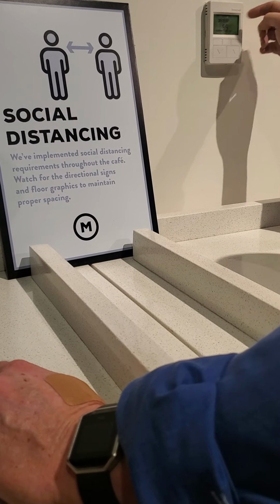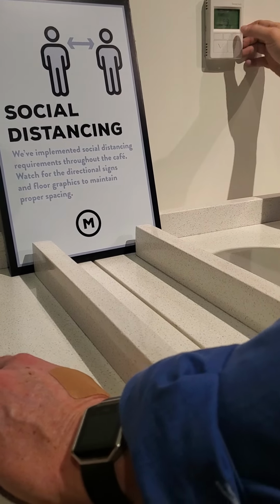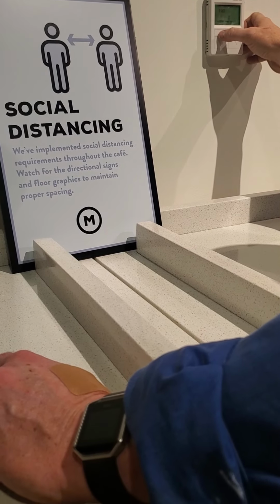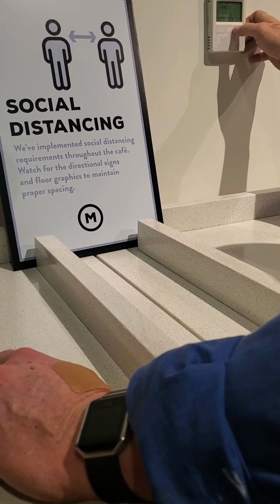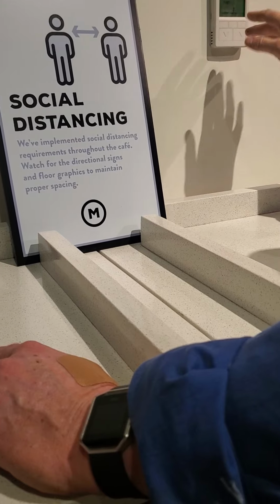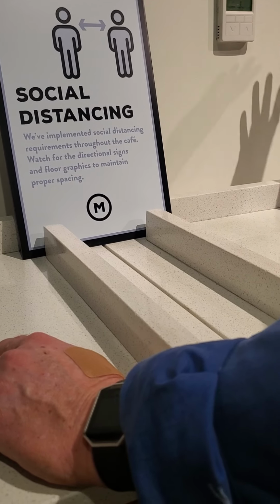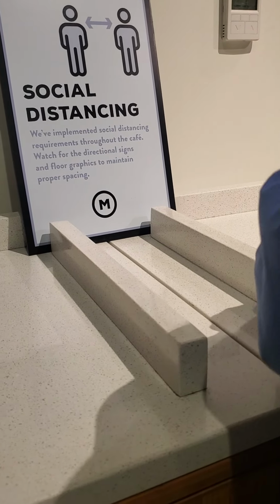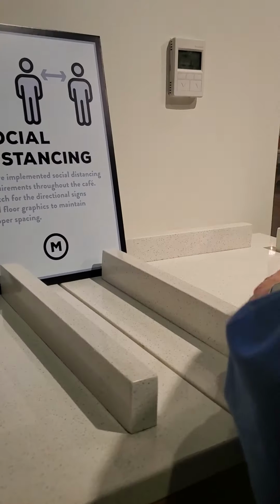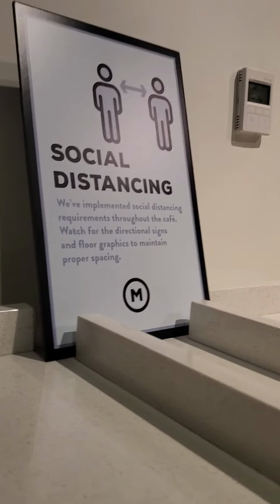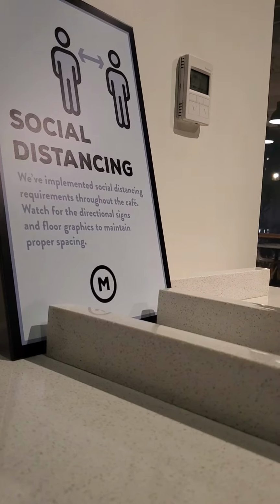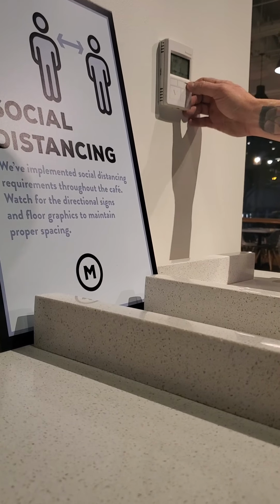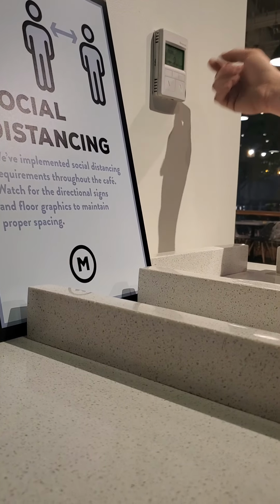Discharge air temperature set point is 55 for cooling. You could mess with these set points, some of them. He's given you access to change some, but others you have to get in with the computer to actually change. The stuff you'd want to change, you have access to. From what I remember, you're not going to change the set points on this changeover or any of that anyway. There's a freeze alarm, it'll tell you if you're in alarm.